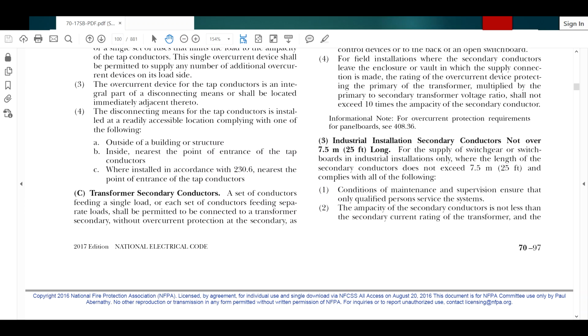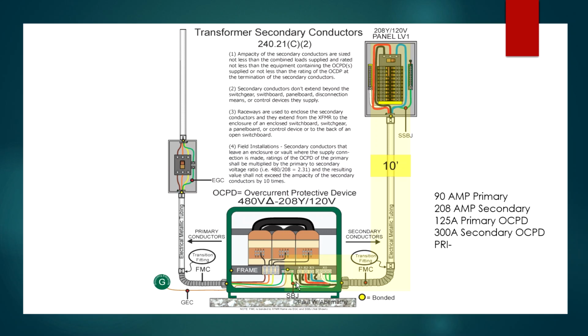Okay, so what are we saying here? So, oops, go back to the video here. So it's saying right here, I don't have to have overcurrent protection right here. All right, that's the whole purpose of this secondary conductor allowance. But if I did have overcurrent protection right here, then I would just treat the conductors on the load side of this protection as feeders, and I would size them to handle the load or whatever. But here we're trying to utilize these secondary conductors which have no overcurrent protection right here. The overcurrent protection is right here, okay? And this protects the panel board if it's a lighting and appliance type of panel board or lighting and power under 408.36, okay? So that's what we're dealing with.